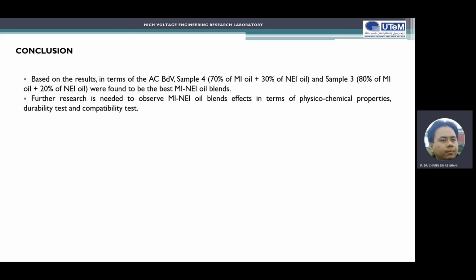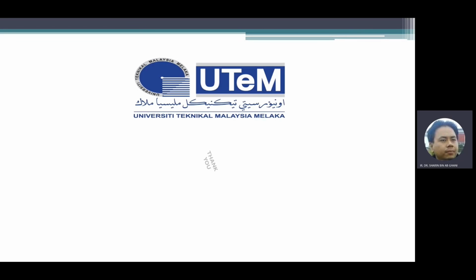All of these have more than 50% mineral insulating oil, because we don't want to reduce it too much. That's why we keep our mineral oil above 50%, and the highest breakdown voltage comes from samples 3 and 4. For further research, we plan to observe the effects of these blended samples in terms of physical-chemical properties, durability tests, and compatibility tests. This is our reference, and thank you very much.